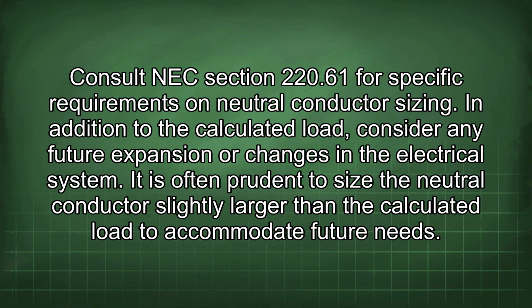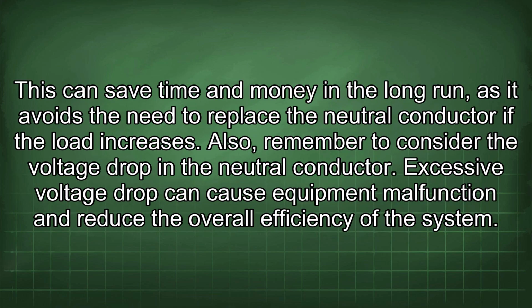In addition to the calculated load, consider any future expansion or changes in the electrical system. It is often prudent to size the neutral conductor slightly larger than the calculated load to accommodate future needs. This can save time and money in the long run, as it avoids the need to replace the neutral conductor if the load increases. Also, remember to consider the voltage drop in the neutral conductor.